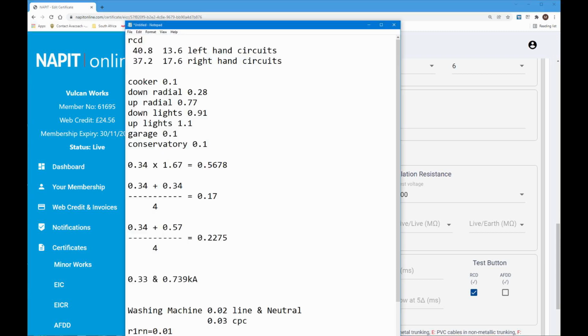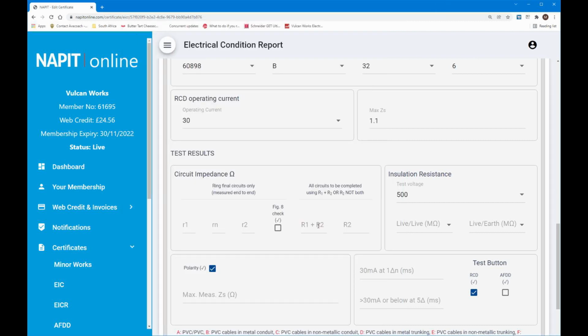So let's bring up my little pad here. These are all the results from the testing. So let's forget the RCD testing for the second. The cooker circuit had a reading of 0.1. So we'll put 0.1 in here. Now the insulation resistance test I did manage to do at 500 volts.